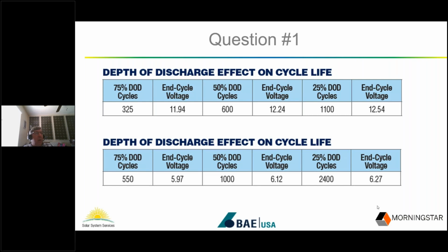Now, on the other hand, if you go to say 50% DoD on those batteries, you're up to about 600 cycles on one, and up to 1,000 on the other. So you've about doubled the cycle life just moving from 75% to 50%, and you double it again going up to 25% or even more in the case of the little 6-volt battery—2,400 cycles. At 2,400 cycles, you're looking at about 10 years, or pushing 10 years, maybe 8 years or so. You're really up there.